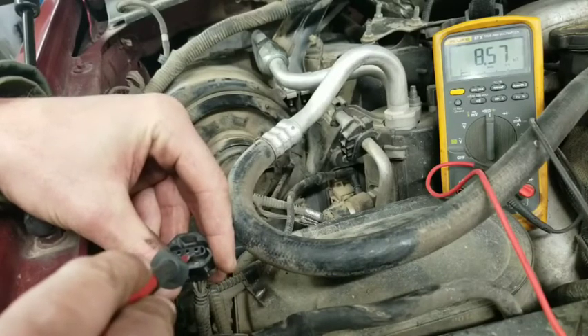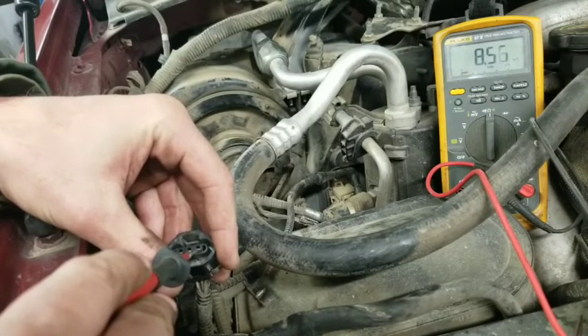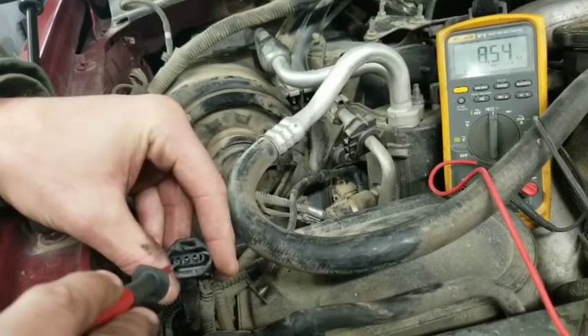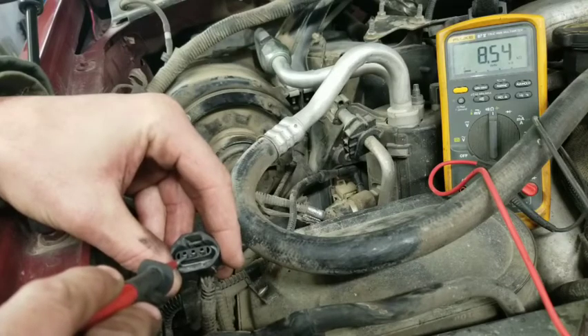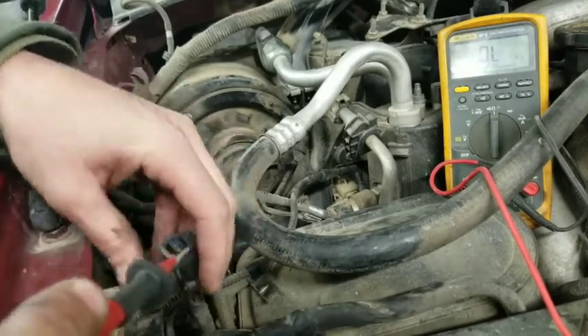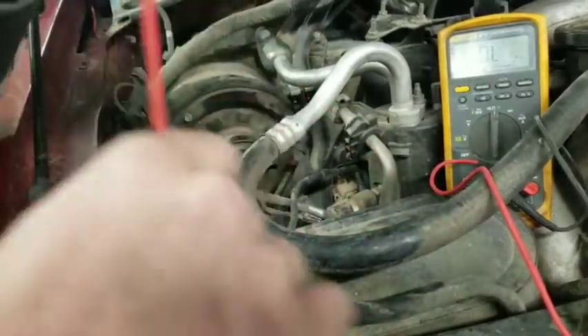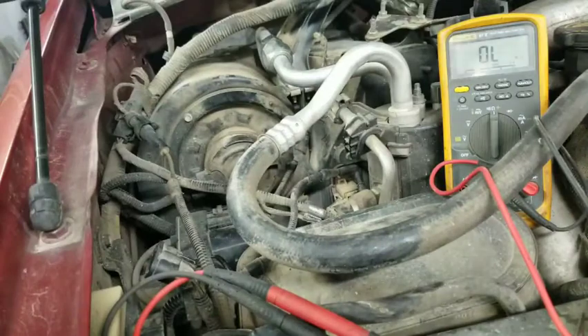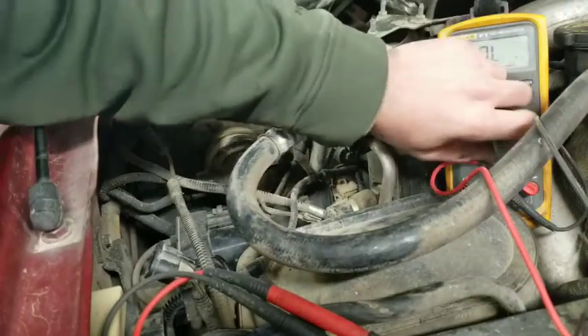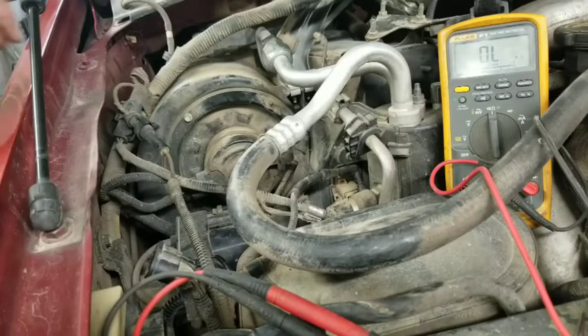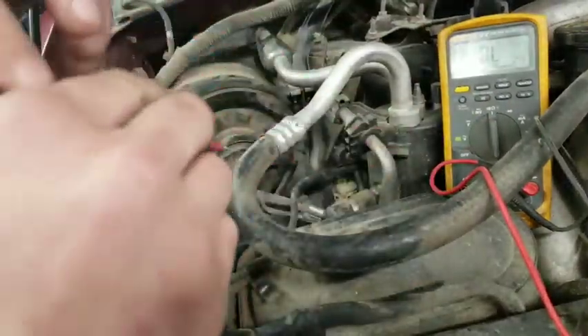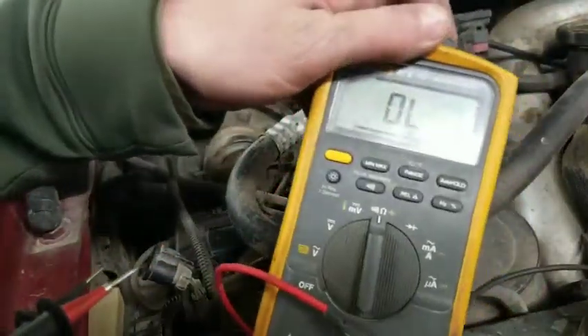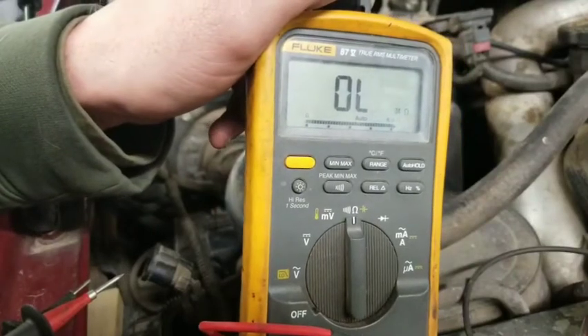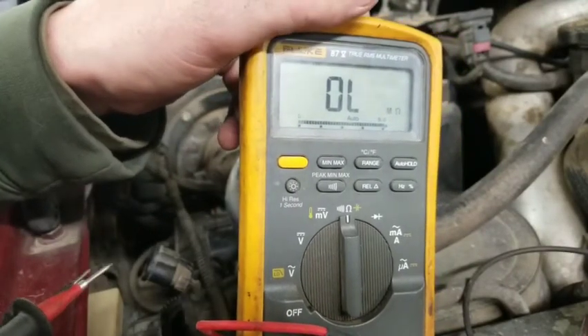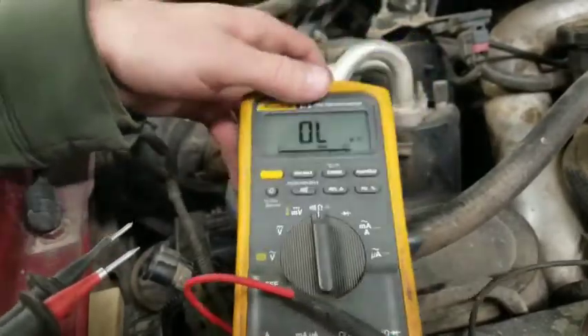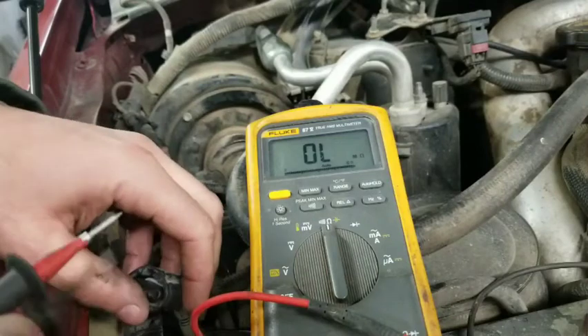We've got about 9,000 ohms, not 8.57. Both meters are reading that way, so it's about 9,000. Still a lot, not quite above the 10,000 they were talking about, but that's enough resistance that it's not actually shorted. They just use that particular number. But notice on this meter, it's reading OL, and that M means mega ohms. The resistance between the two is so high it doesn't know how to read it.